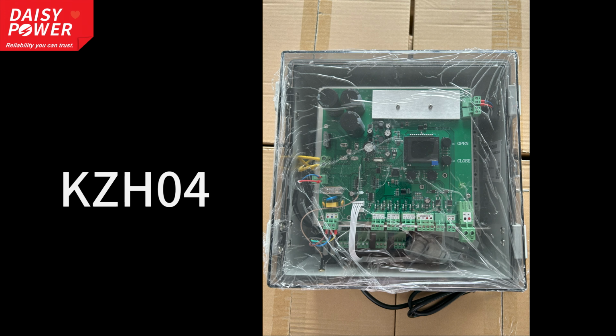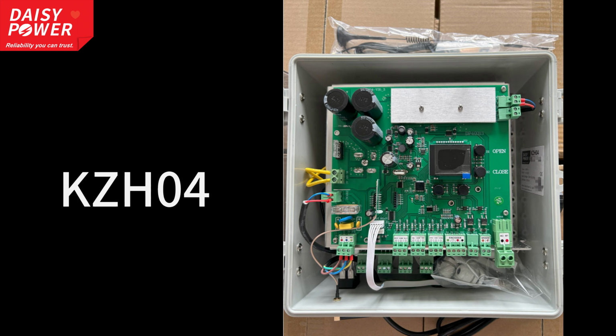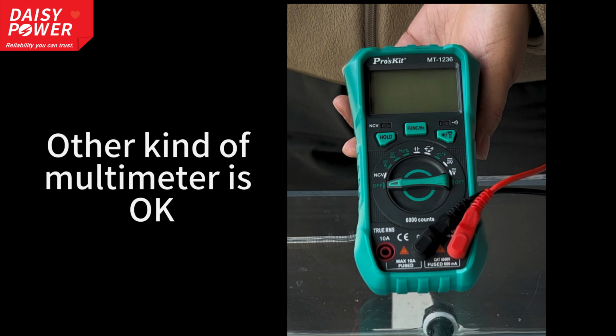This is Daisy Power KZH04 control box. If the control box doesn't respond when you push any button, or the screen image stands still, we can check the voltages at some places to diagnose the problem. First of all, a multimeter is required. Checking process should follow the circuit flow.